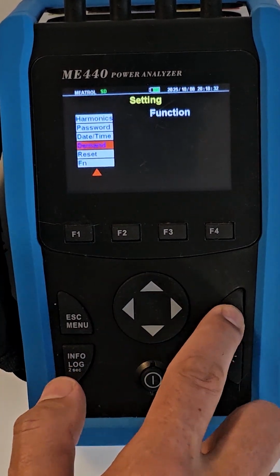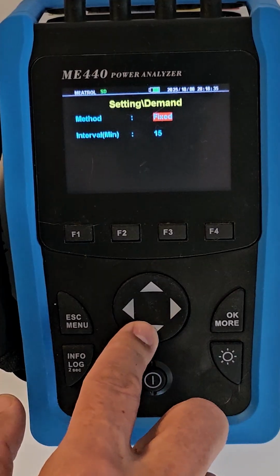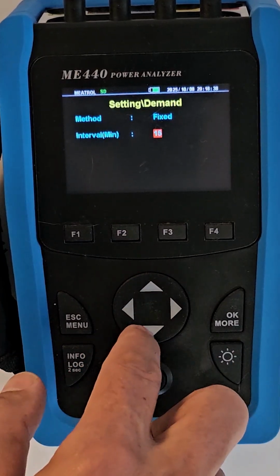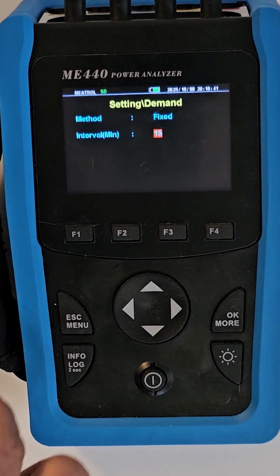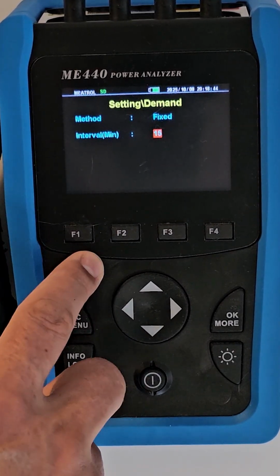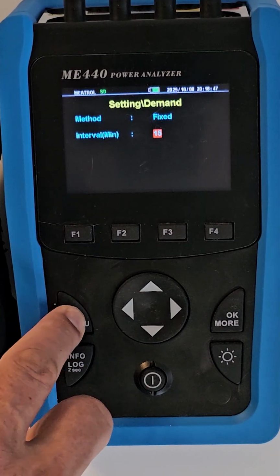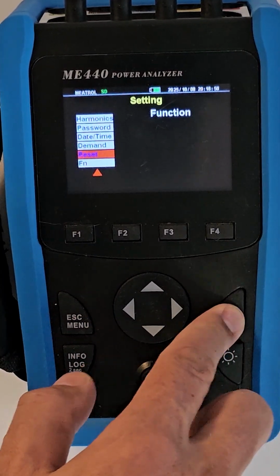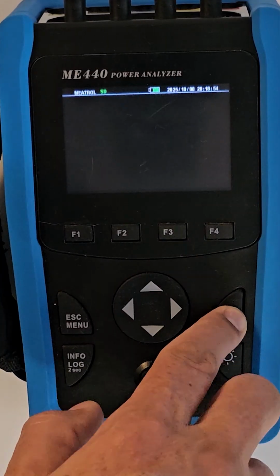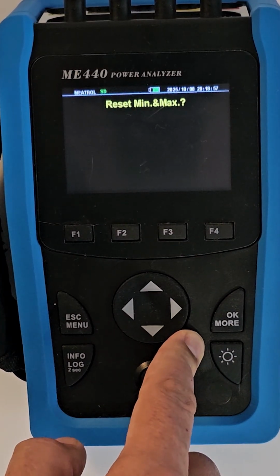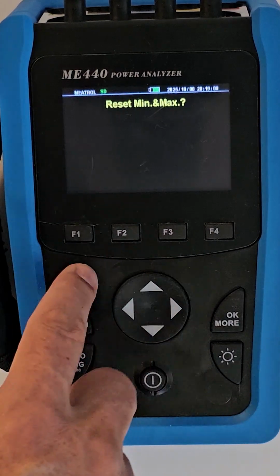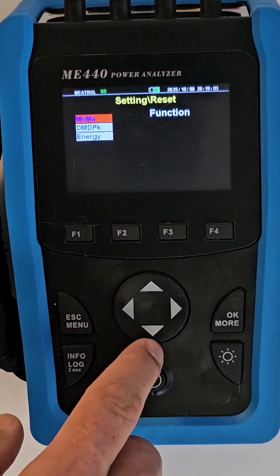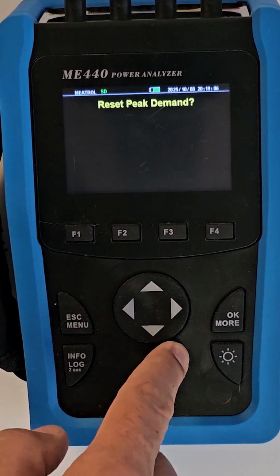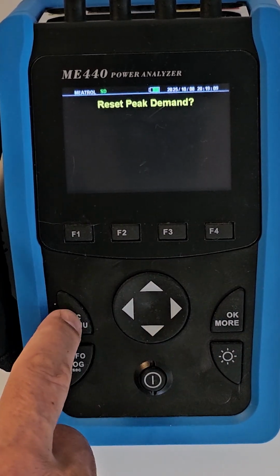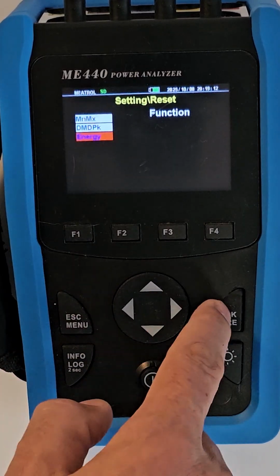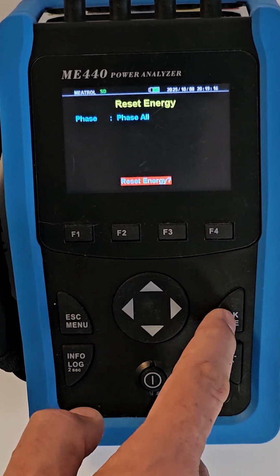Okay, so if we go into our demand screen, you can set it to be either fixed or sliding, and you can also set the period here, either 15 or 30 is typically the period that maximum demand is measured in. Okay, and then if we go into the reset menu, you can reset the minimum and maximum values of your power and current. It's also a good idea to reset this before you start logging. And here you can reset your peak maximum demand, and also your energy that was logged over that period.